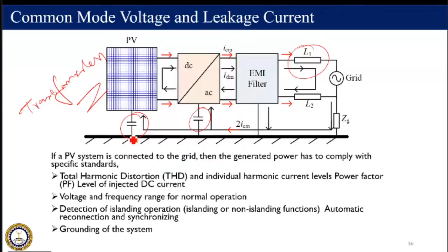This is very common when we have a PV connected to the grid without a transformer, that is, in a transformerless inverter. Right? When we remove the transformer, the ground of both the PV and the grid is the same. So this is going to establish a path called a common mode path, and there will be an additional current called leakage current, which is going to affect personal safety, and also distort the grid current. That happens because of the parasitic capacitance you can see here, together with the common grounding, and it is going to affect the power quality.